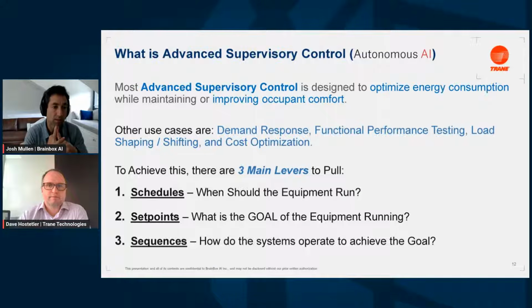Let's say you're doing seasonal maintenance. You have a portfolio of big box stores that have 40 rooftop units on each one, and you want to do seasonal heating or cooling checks. So at night, you run those pieces of equipment through each stage of cooling or heating and issue that technician a report so they know what they're getting into when they go out there. After the work is performed, you run that equipment again at night so no one is interrupted, no comfort is affected, and check to see if that work has been performed properly.